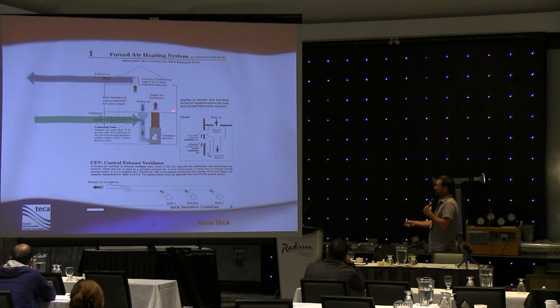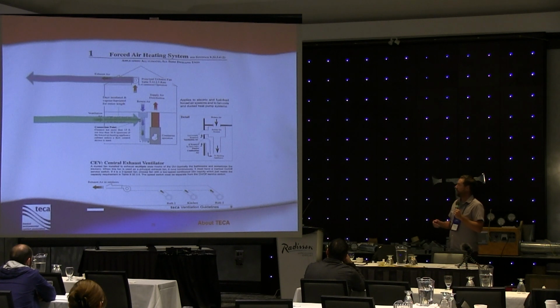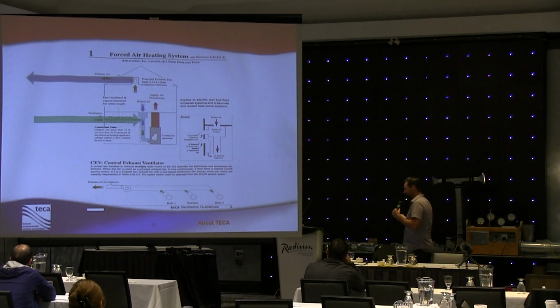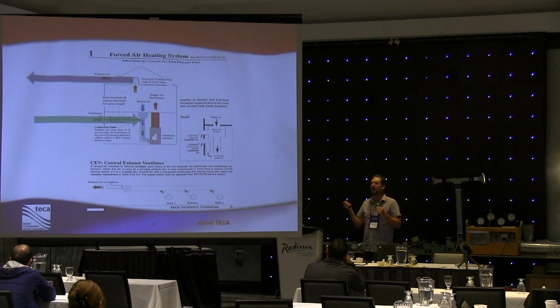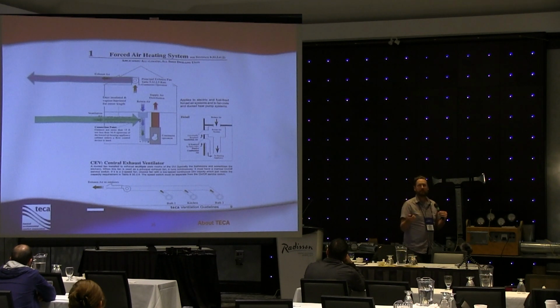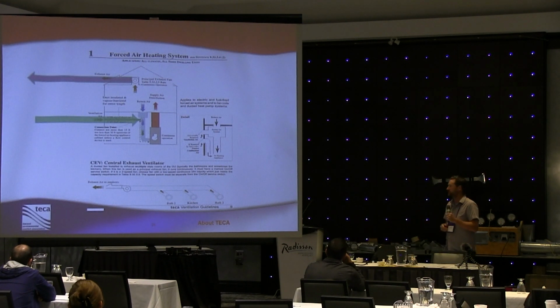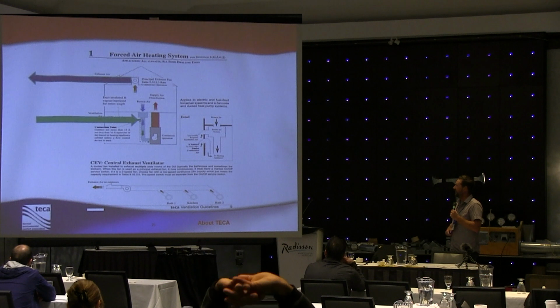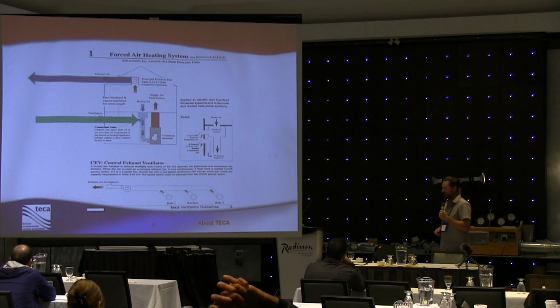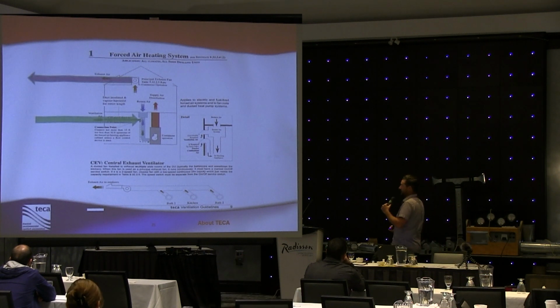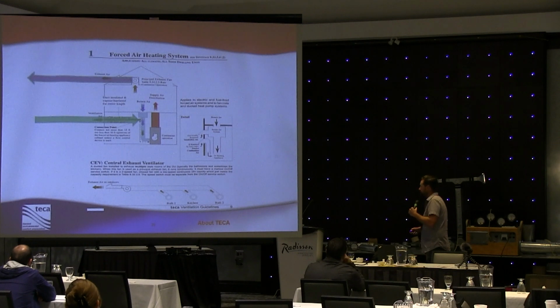And finally, we are exhausting air that we've already paid to condition. So whether we've heated that air in the winter or cooled it in the summer, there's a cost to that as well. So we don't want to overventilate. It's a big concern of ours. We don't want to overventilate. We don't want to waste that energy, and we want to make sure that we're meeting the minimum rate so that we can keep that building envelope fresh and healthy.